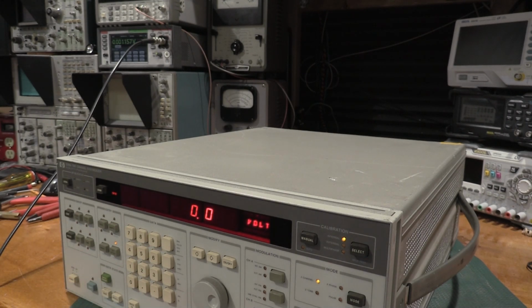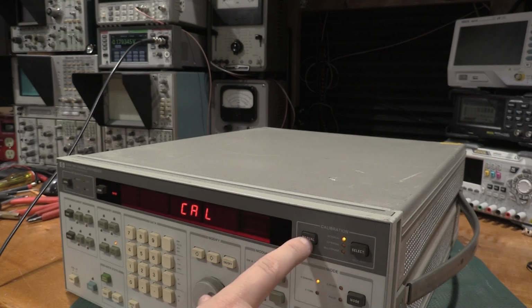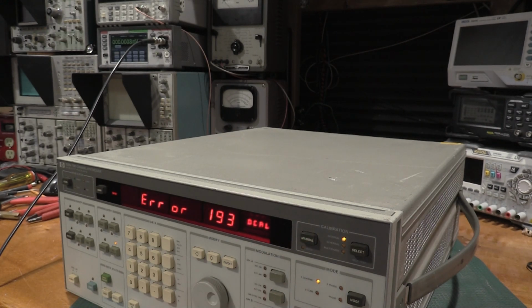So the problem is on our positive DC offset setting, if I go to 0.1, it won't align. Error 193. Go back to negative 0.1. Gives us 193. We dial up. If I go to 1 volt, it'll stop erroring. And it makes a liar out of me.